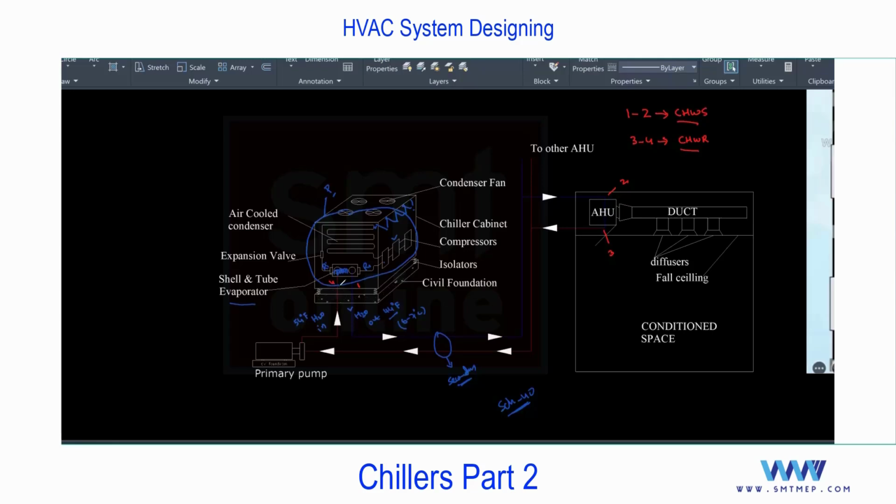Next, you see, in as cold water loses the heat to the refrigerant, out as chill water, and this chill water with the insulated pipe is going to supply to one more heat exchanger, inside what? AHU. And you know what AHU is. It can be AHU or it can be FCU as per the requirement. In actual practice, in this drawing you'll find one AHU, but the pipe will continue and can connect to n number of FCUs or AHUs as per the capacity of the system. So this chill water will enter the cooling coil of the AHU. And you know what will happen in the AHU on the air side? Same as a ductable split.